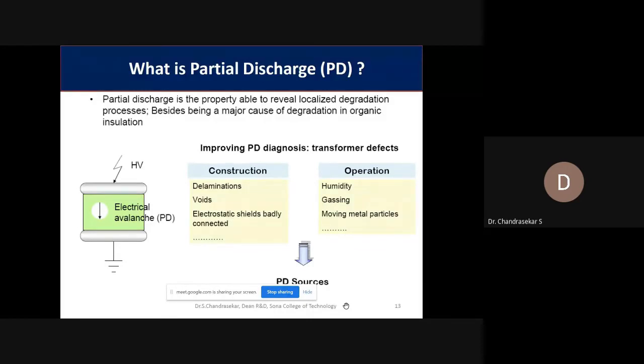It is mainly because of any delamination, or any presence of void, or any bad connection. So all these things are the major causes for the PD occurring inside the insulation. Okay, there are different types of PDs. One way we can classify it is as internal partial discharge and corona partial discharge or surface partial discharge.